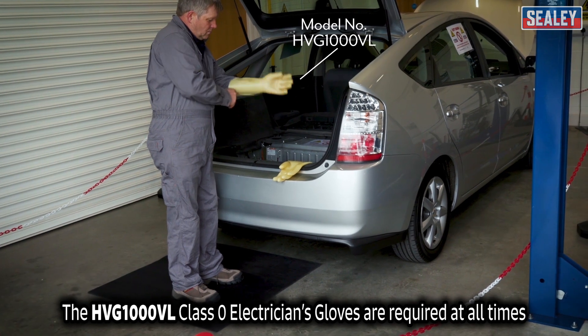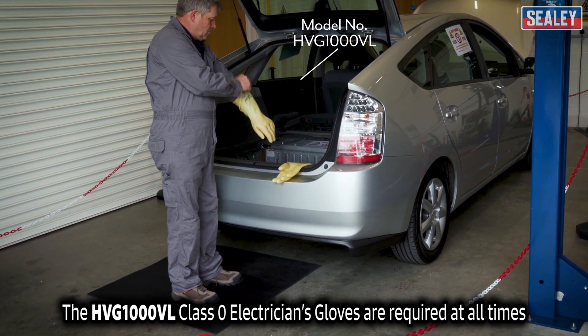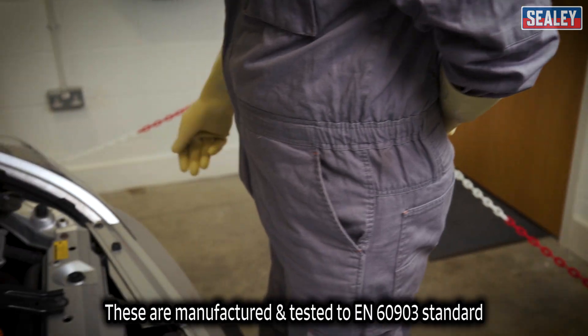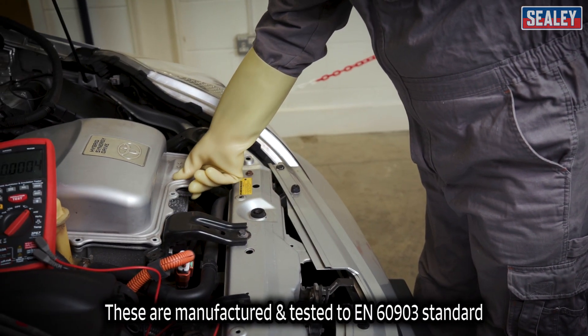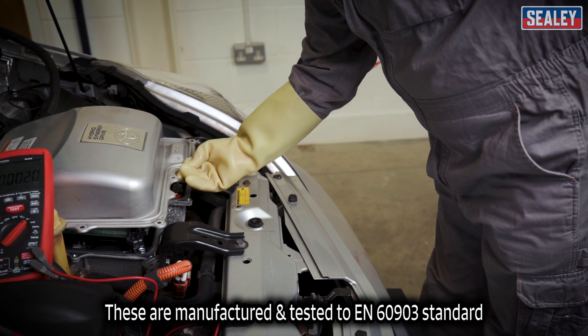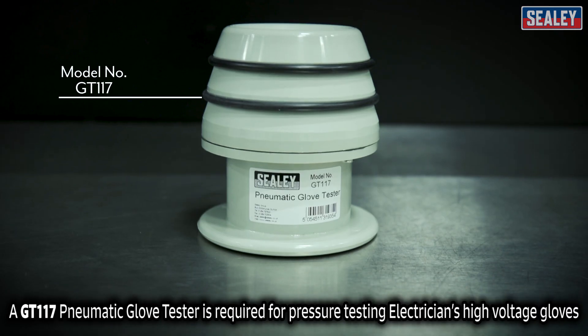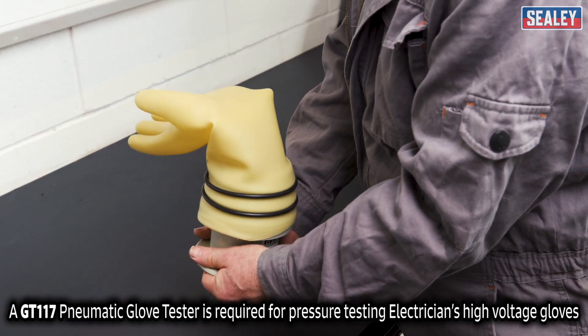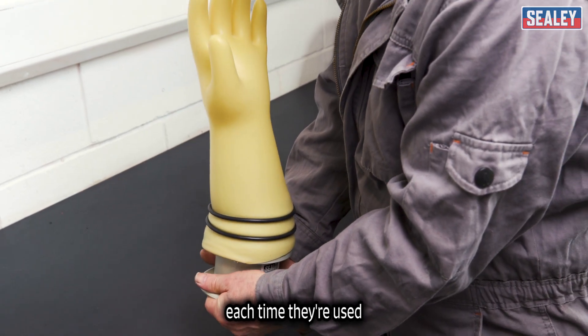HVG1000VL class 0 electrician's gloves are required at all times when working on high voltage systems. These are manufactured and tested to EN60903 standard. A GT117 pneumatic glove tester is required for pressure testing the electrician's high voltage gloves each time they're used.